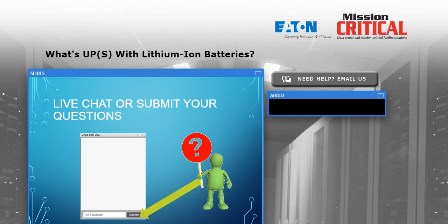And that sounds like a lot, but we do have some clients that use a lot of UPS and a lot of long-duration batteries. And in that case, a positive pressure ventilation system with controls on the fans and controls on the UPS and battery charger would all have to be put in place, similar to what we see with large valve-regulated installations. That means that the room is going to need a ventilation fan system that runs all the time, also backed up by the UPS. If a ventilation fan fails, the UPS should then be commanded to stop charging the battery so that we don't add any chance of extra gases building up in the room, etc.